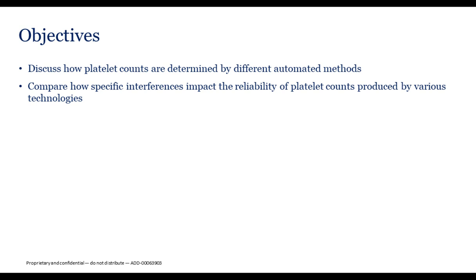A disclosure statement: this speaker program is sponsored by and on behalf of Abbott Diagnostics, and the content of this presentation is consistent with all applicable FDA requirements. Today's hematology analyzers utilize various methods for enumerating platelets, including electrical impedance, light scatter, fluorescence, and immunological recognition with monoclonal antibodies. While these approaches generally produce an accurate platelet count in the majority of samples, circulating abnormalities have been shown to negatively affect the reliability of reported results.